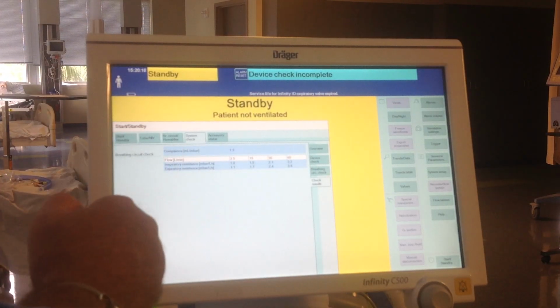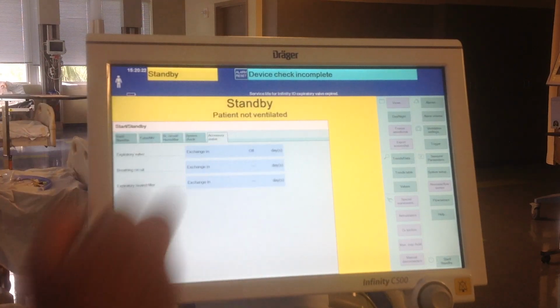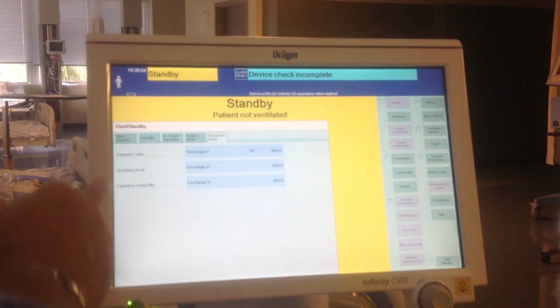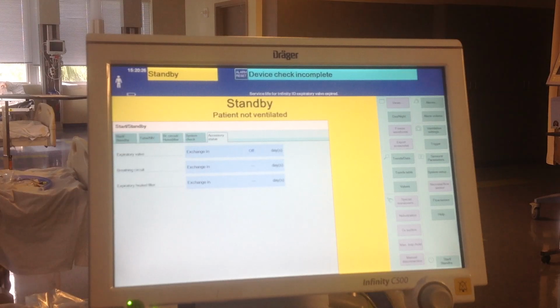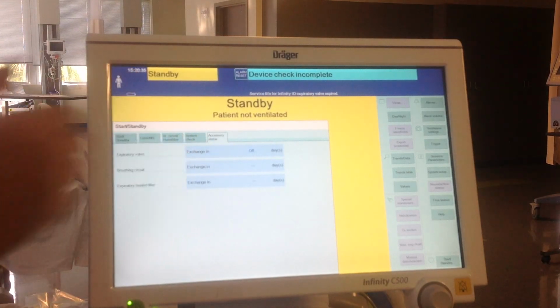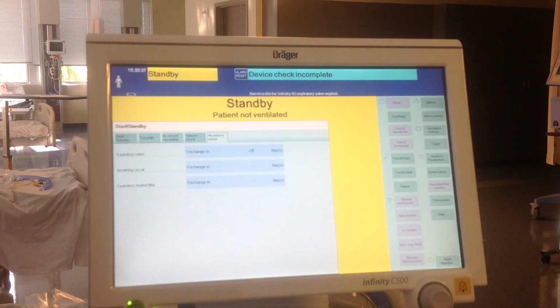This is showing you the compliance, also the flow, inspiratory, all the resistance, but also the accessory use. What this screen will show you is when you need to change the expiratory valve, when you should exchange the breathing circuit, when you should exchange the expiratory heated filter. Okay, ours do not go on patients. I wanted to just show you where that screen was. And that is the pre-use check on the Draeger Evita Infinity C500.